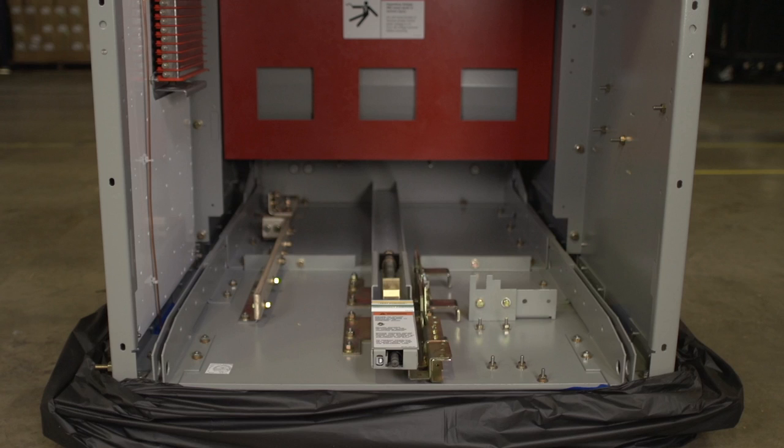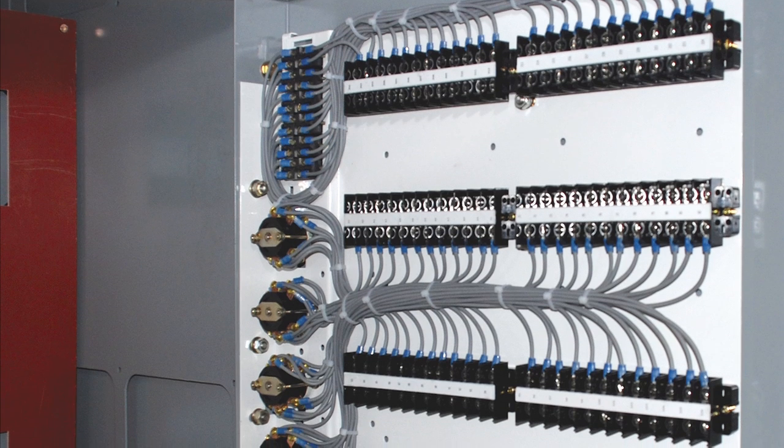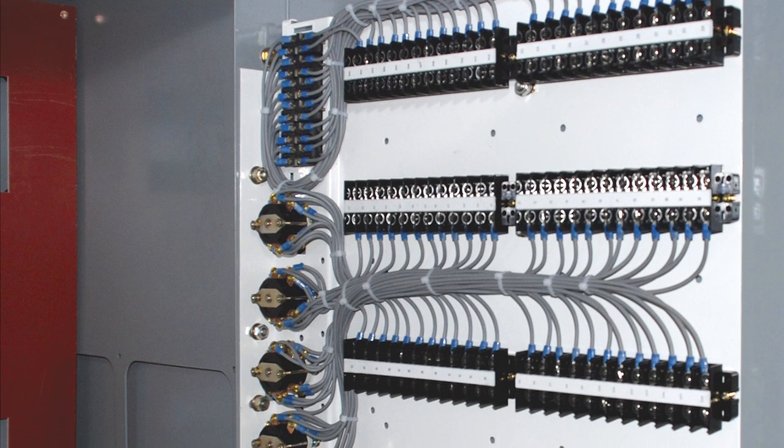This equipment ground is used for grounding the controls and protective relays, as well as the switchgear structure. Running along the right and left side of this section are passageways for wiring. They go through the bottom and up into the auxiliary compartment.